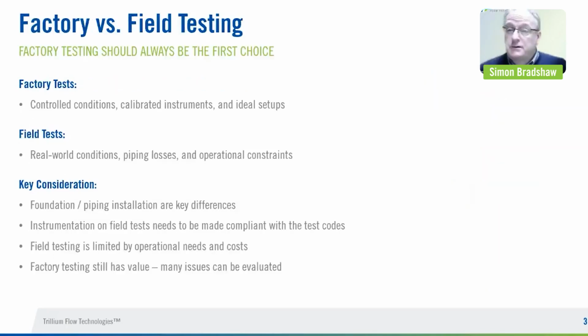And then finally, factory versus field testing. I saw a question on this in the chat. Factory testing should always be the first choice. You have controlled conditions, you have fully calibrated instruments to the levels that you need, and you can control the variability to the levels that are required within the test standard. As soon as you go to field tests, your instruments are probably not good enough. Your piping may not be good enough. So at the very least, you're likely to have to install some better quality instrumentation for that field testing.